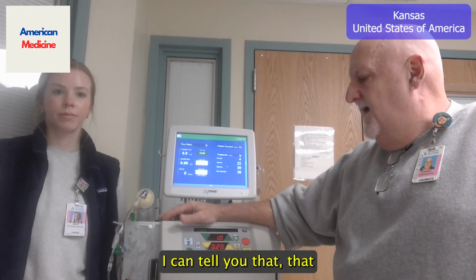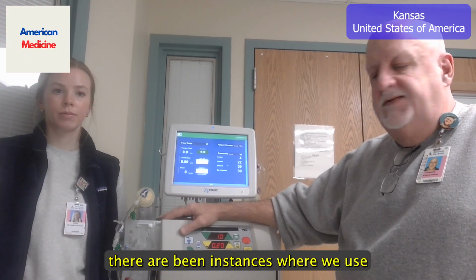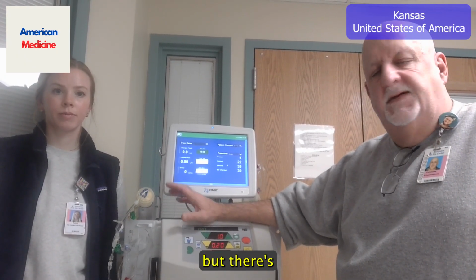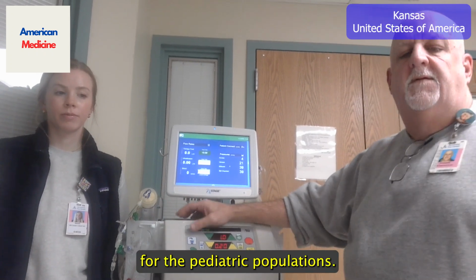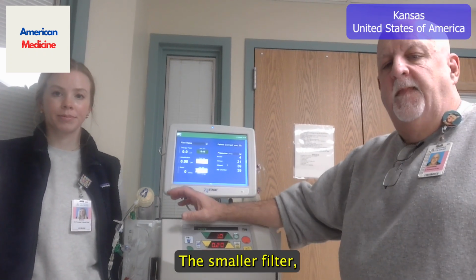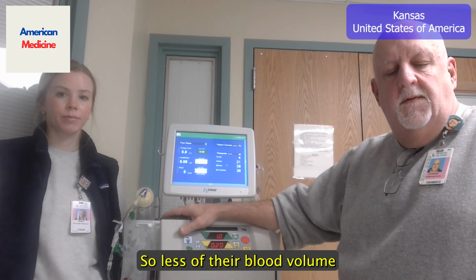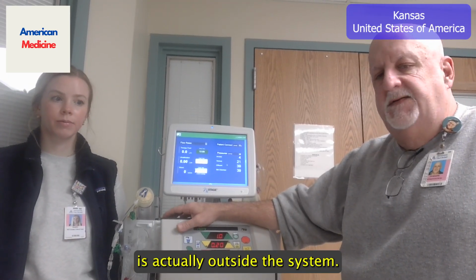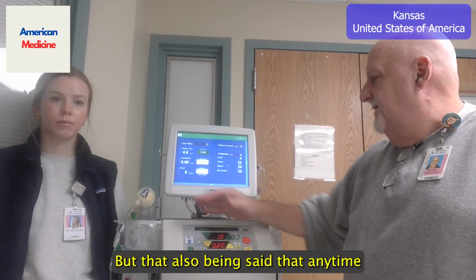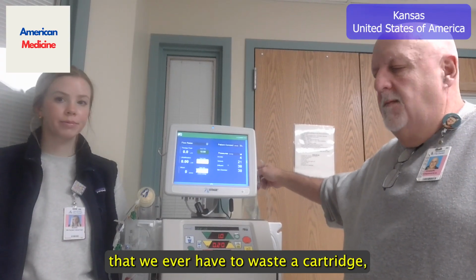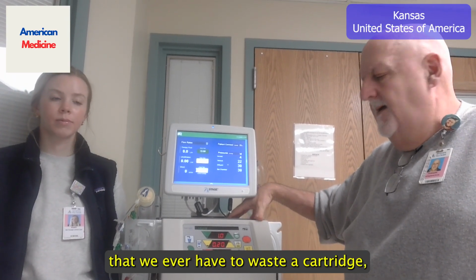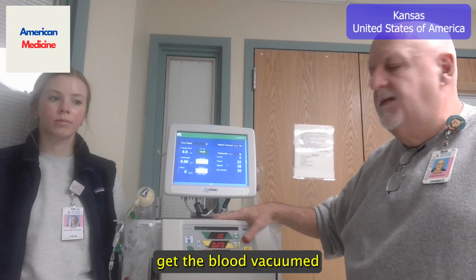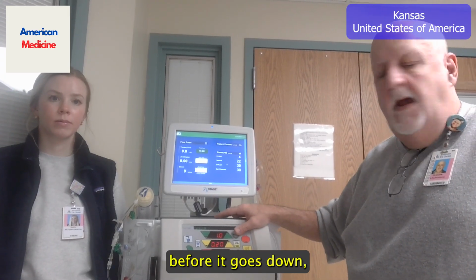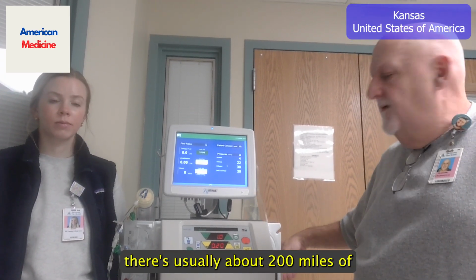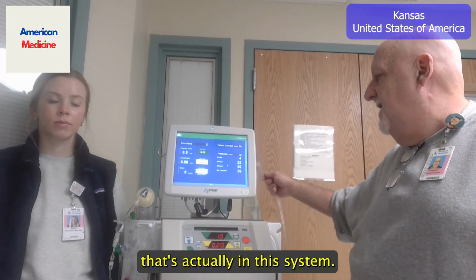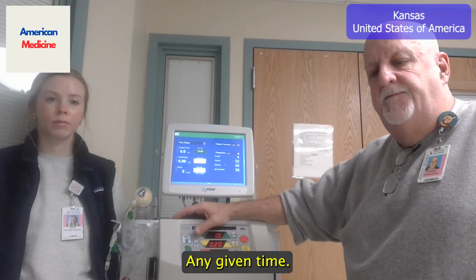I can tell you that there have been instances where we use this on a pediatric population, but it's a different filter that we use for the pediatric population. It's a smaller filter. It's smaller tubing, so less of their blood volume is actually outside the system. That also being said, any time we ever have to waste a cartridge, if we can't get the blood back to him before it goes down, there's usually about 200 mLs of blood outside the system at any given time.